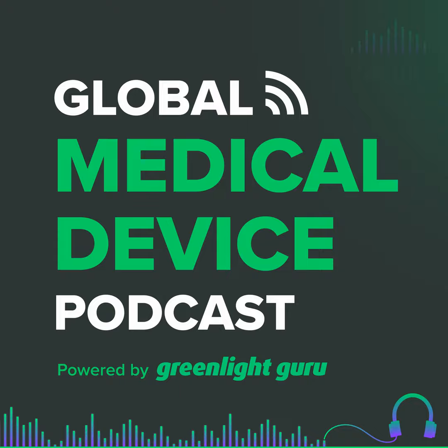And one other thing that I would just point out before we start to wrap this up, Etienne, is in those situations where your device is a non-significant risk device and you are what we call IDE exempt and you do not have to go to the FDA prior to your clinical trial. I think it's a good idea to, but you're not required to. In that event, keep in mind that the only thing standing between the patient and the safety of your device is the IRB. There is no FDA in this particular case.